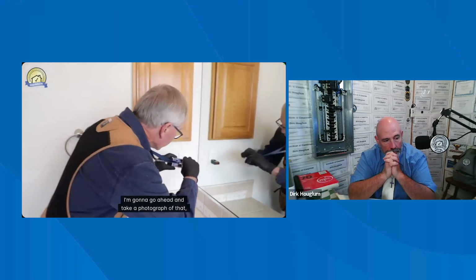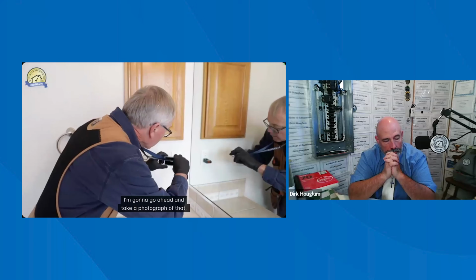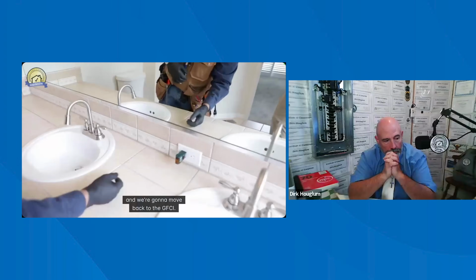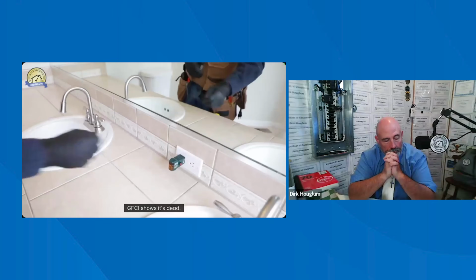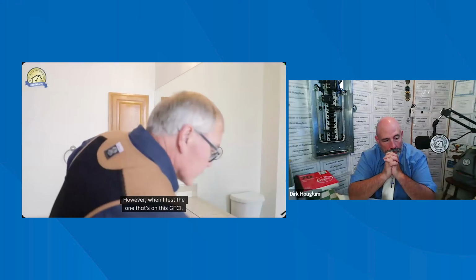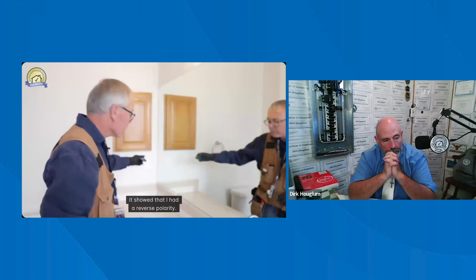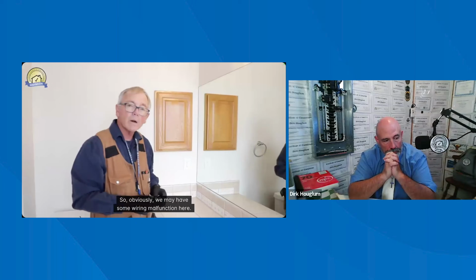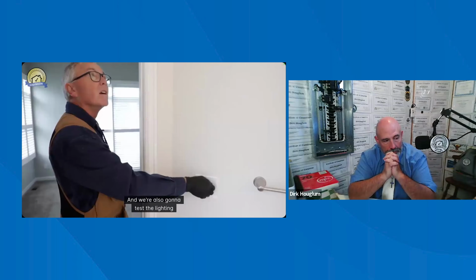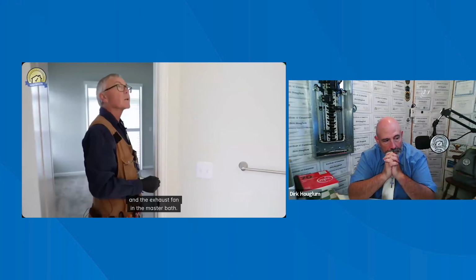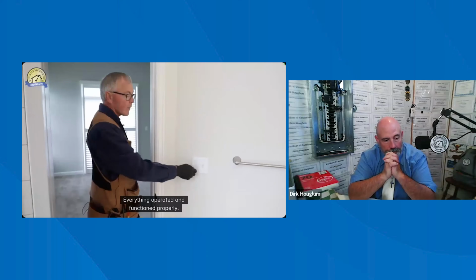So we actually have an issue here. I'm going to go ahead and take a photograph of that. I'm going to move back to the GFCI. The GFCI shows it's dead. However, when I test the one that's on this GFCI, it showed that I had a reverse polarity. So obviously we may have some wiring malfunction here. We're also going to test the lighting and the exhaust fan in the master bath. Everything operated and functioned properly.